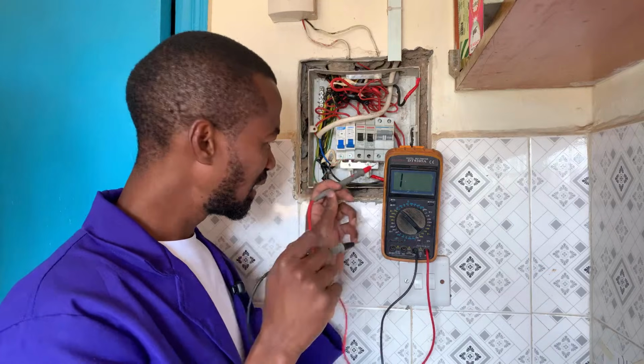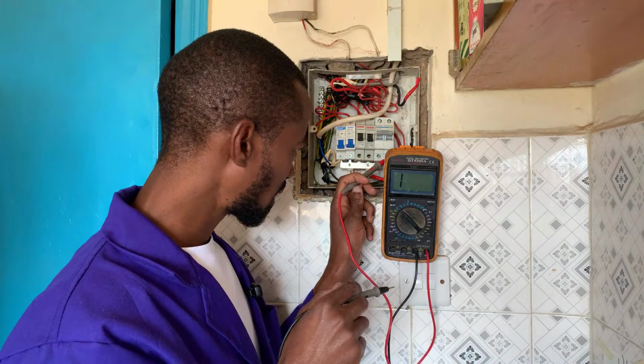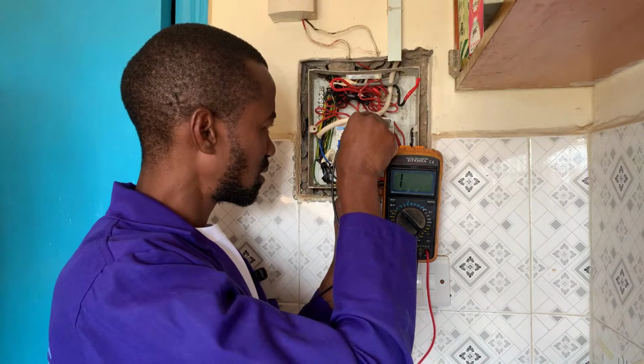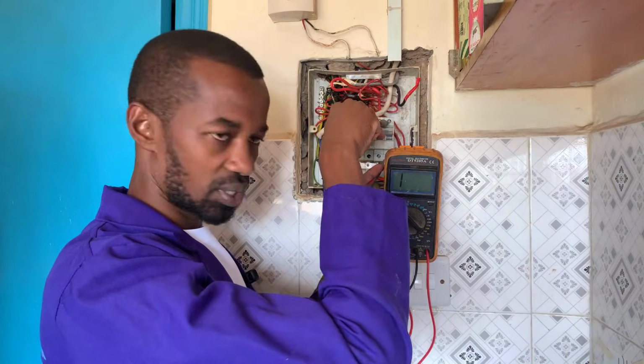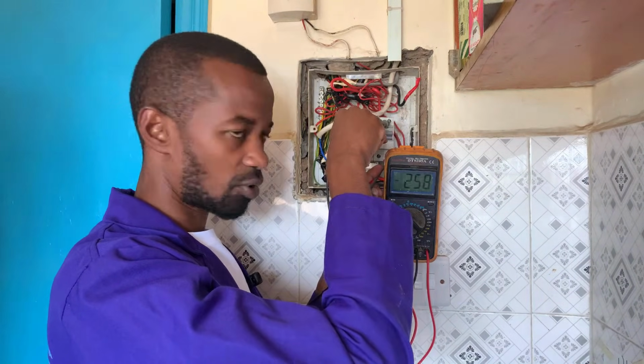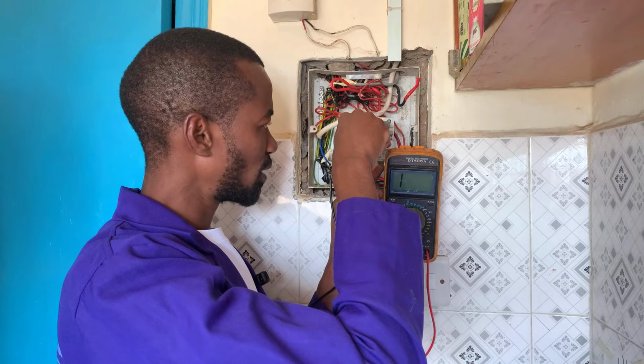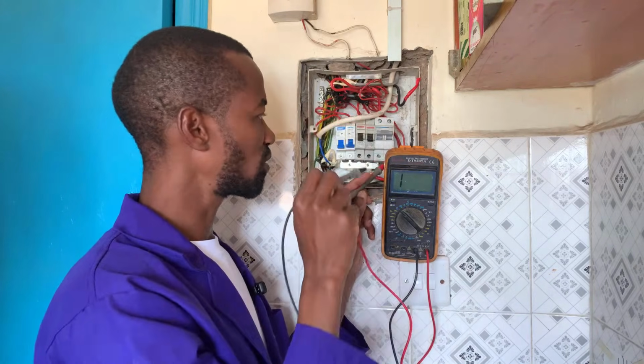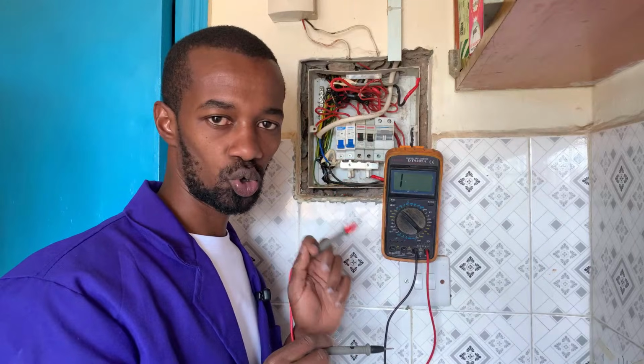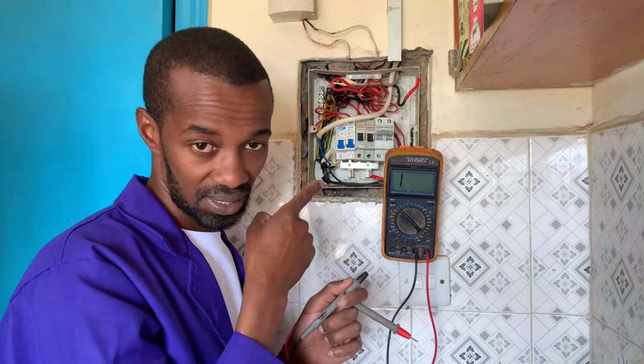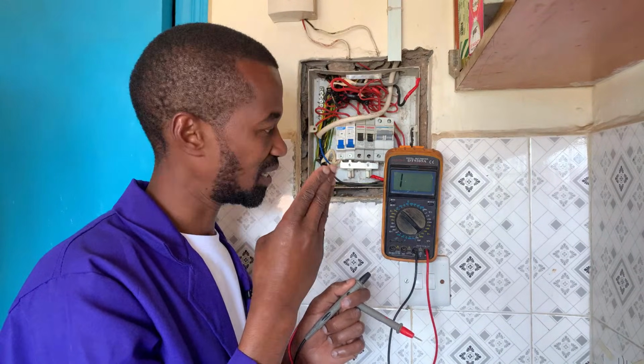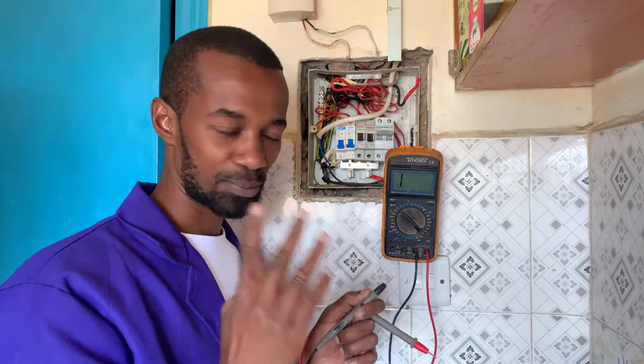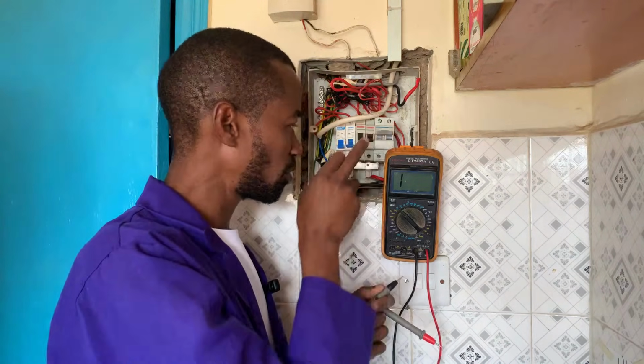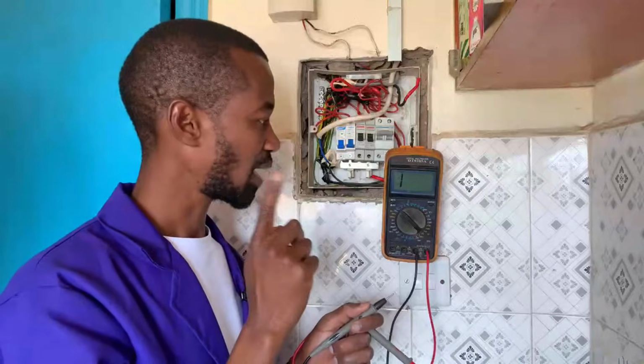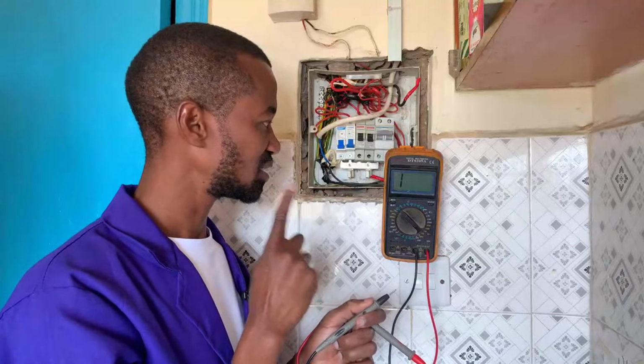Unless we really push it harder, we can tell that it is not really responding, because I have placed the probes in contact with the terminals on both the incoming and the outgoing, and this misbehavior is coming from the neutral side. That is why we suspected that indeed this double pole MCB was having a problem, and indeed it is.